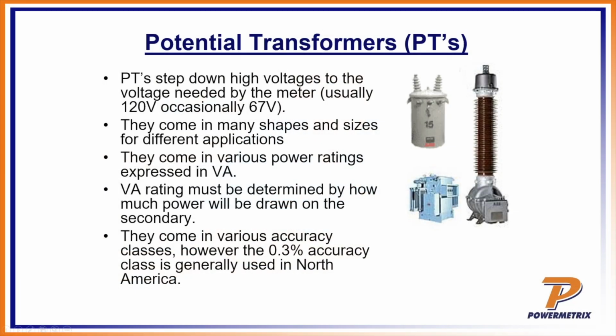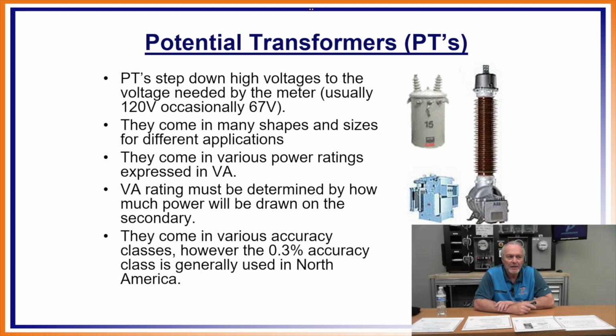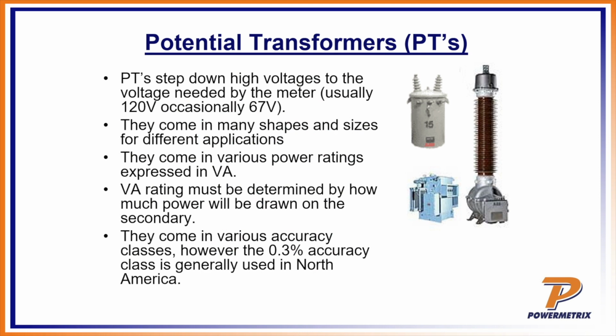Potential transformers, PTs, we just talked about a little bit. They're going to step down the voltage, and like it says here, you usually want to have 120 volts, sometimes down in the 60s, but most of the time you're trying to get to 120 volts. So if you've got a 480 volt and you want to get to 120, you would just take a fourth of that and use a 4-to-1 step-down PT transformer. They come in a lot of shapes and sizes. Remember, we talked about this in our last class, where we talked about testing the PTs. We said that they're rated in VA, so that's what you have to look at on them. The VA rating must be determined by how much power will be drawn on the secondary. So you rate them off the amount of power, the VA, and that is how they're sized.